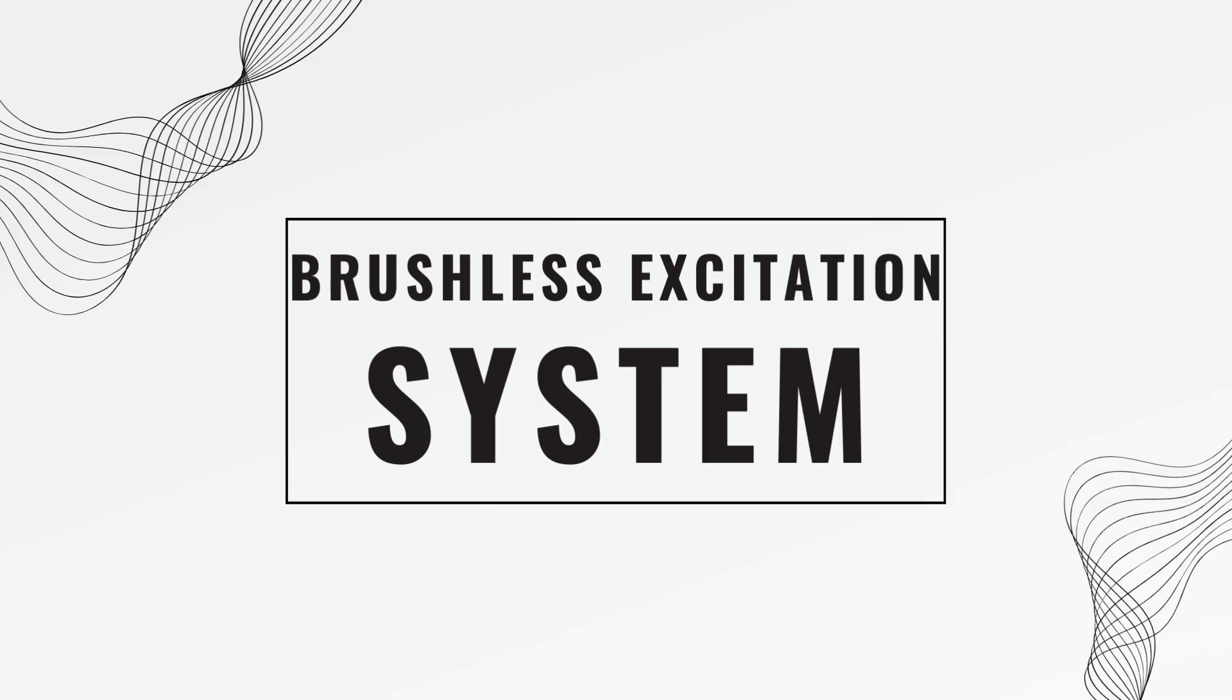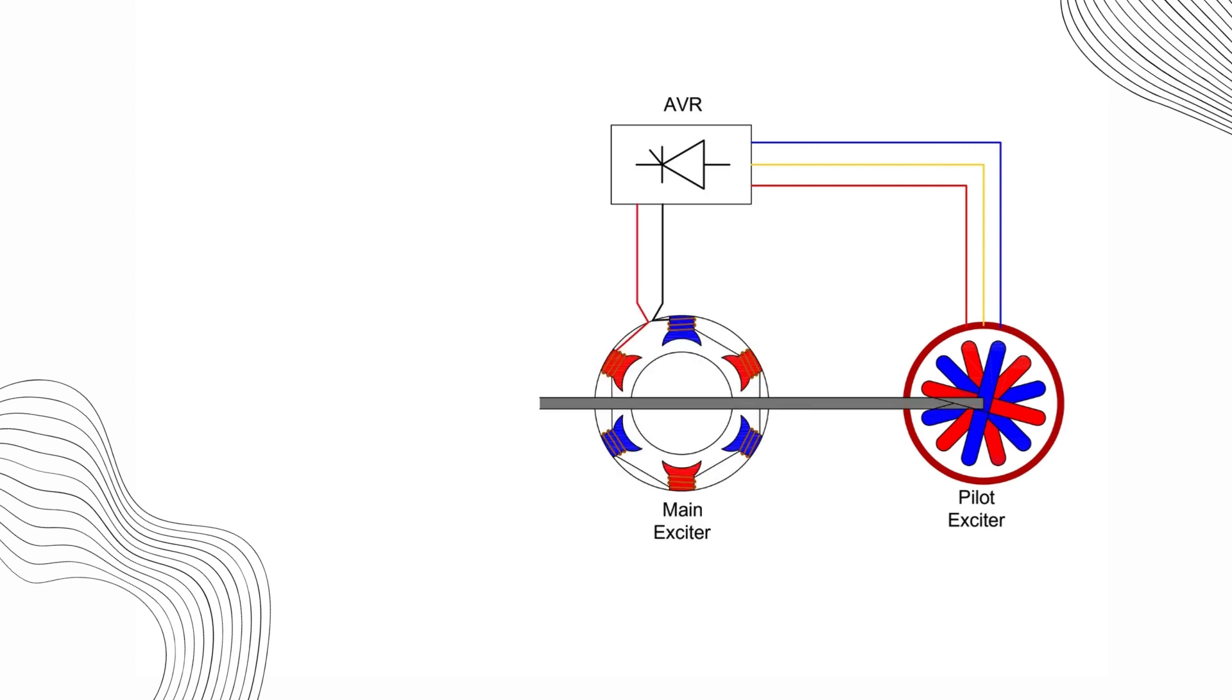In a brushless excitation system, there are 4 main components: the 16-pole permanent magnet generator, or pilot exciter, the automatic voltage regulator, or AVR, the 6-pole main exciter, and the diode rectifier wheel.